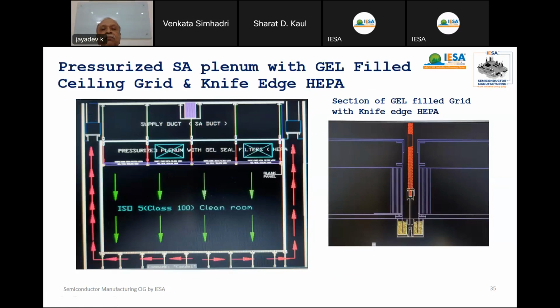This is another type of gel-filled ceiling grid. Most of the people may not be using this. Very rarely we use it. But this is another important thing where there is a confinement, a space problem. This is the top portion of the chamber, and here are the HEPA filters fixed in this. Okay? And this is a pressurized chamber. So we supply pressurized air here, and you have to take more care so that pressurized air should not leak through the joints. So for that, you can use it for ISO 5.